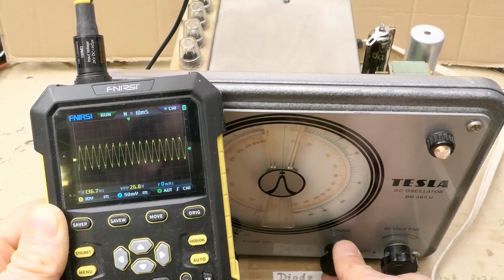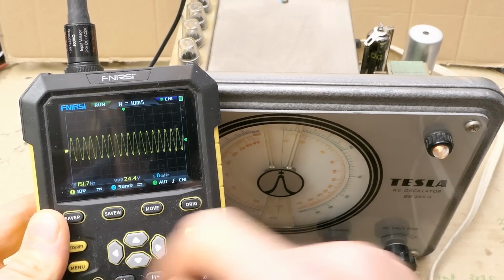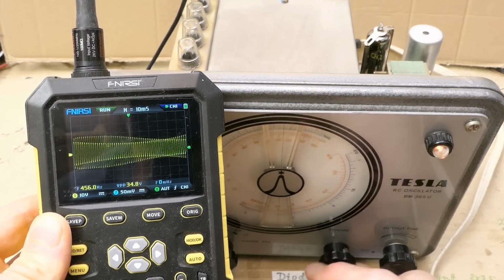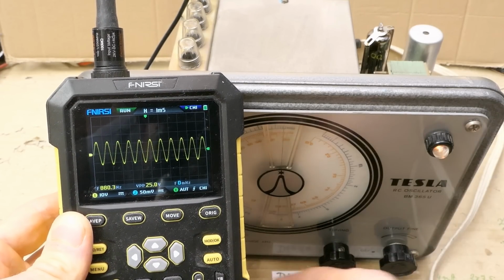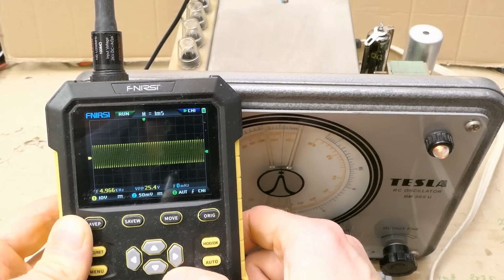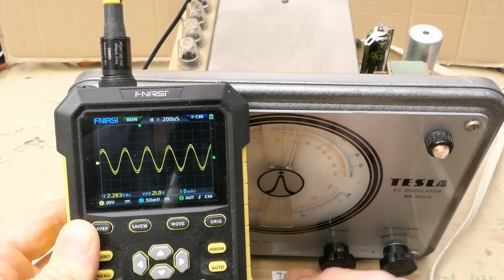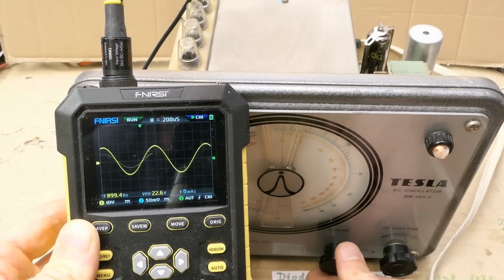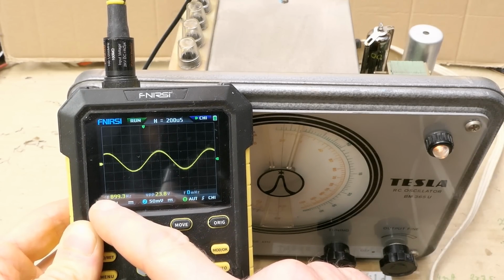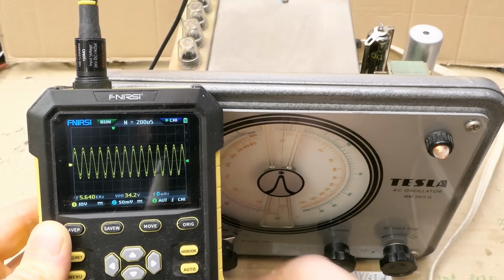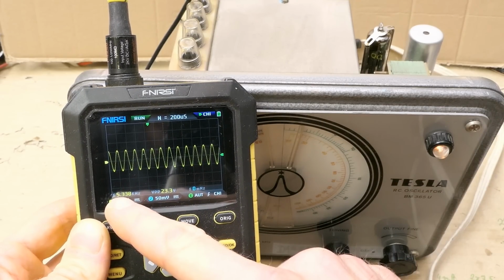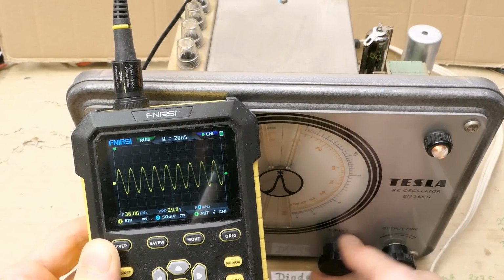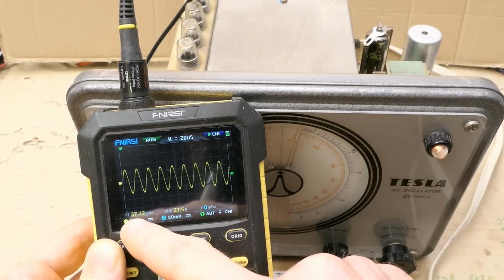25 Hz, 24 point something, not bad. The second range should go from 150 Hz, 151, nice. It's quite close, all the way to 0.9 kHz. Actually quite close to 900 Hz. The third range, the top of it is 5 kHz, very close, and the bottom of it 0.9 kHz. Super close actually, that's virtually 900 Hz. And the highest range should go from 5.4 kHz, super close, to 30 kHz. It actually goes a bit farther, all the way to 37 if you need. This seems like all 4 ranges are working here.